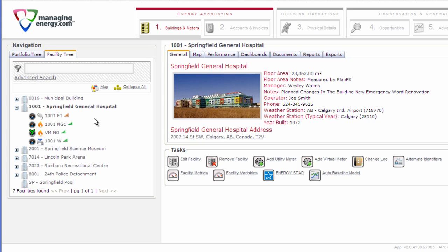facility owner. The second category is virtual meters, for which the readings are calculated based on physical meters and/or other virtual meters. A virtual meter can be thought of as a location where we wish we had a meter, perhaps to recover costs from an unmetered tenant or to allocate costs to an internal cost center. The periodic readings and costs are calculated based on other meters rather than actually collected or invoiced by a utility company. Regardless of the type of meter you are defining, it is important to make sure that meter information is complete and accurate for future analysis.